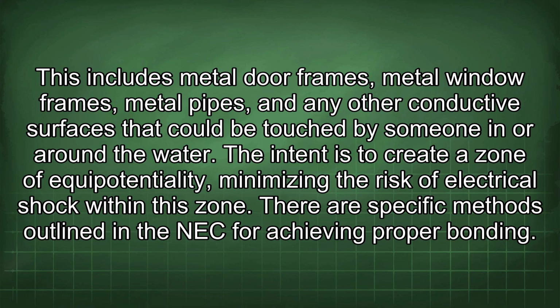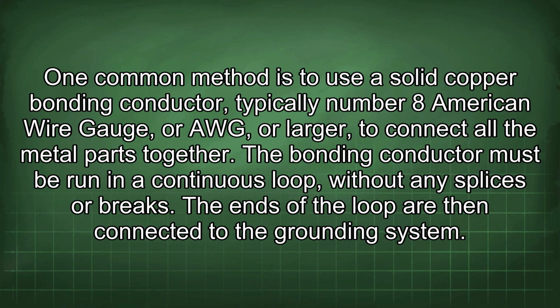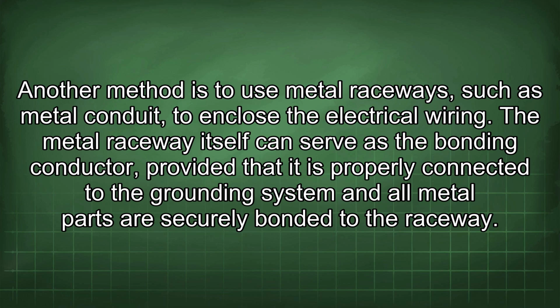There are specific methods outlined in the NEC for achieving proper bonding. One common method is to use a solid copper bonding conductor, typically number 8 American wire gauge, or AWG, or larger, to connect all the metal parts together. The bonding conductor must be run in a continuous loop, without any splices or breaks. The ends of the loop are then connected to the grounding system. Another method is to use metal raceways, such as metal conduit, to enclose the electrical wiring. The metal raceway itself can serve as the bonding conductor, provided that it is properly connected to the grounding system and all metal parts are securely bonded to the raceway.